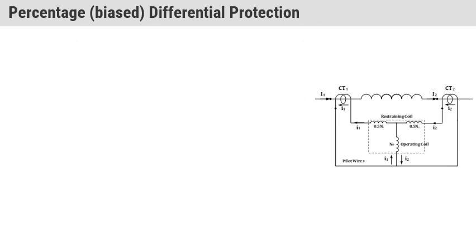Hello student. In the last lecture, we discussed percentage or biased differential protection. This is the advanced, improved version of the simple differential protection. In this particular arrangement, what we have done is add restraining coils.